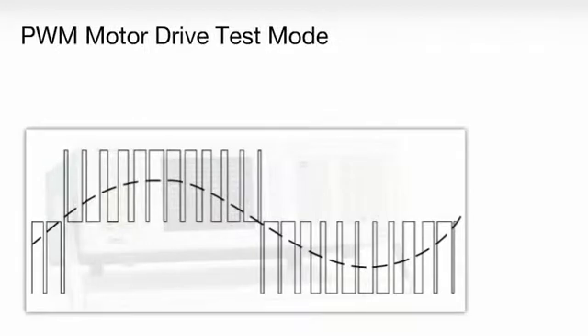Configuring a power analyzer to measure highly modulated PWM waveforms can be frustrating. You get quick results by letting the PA-4000 take care of filter settings and timing.